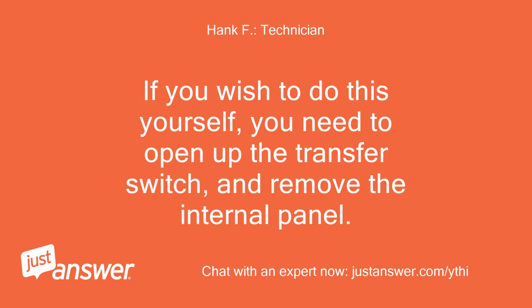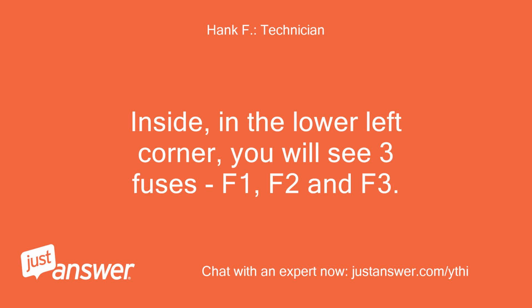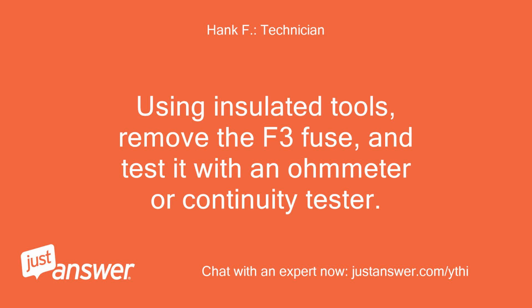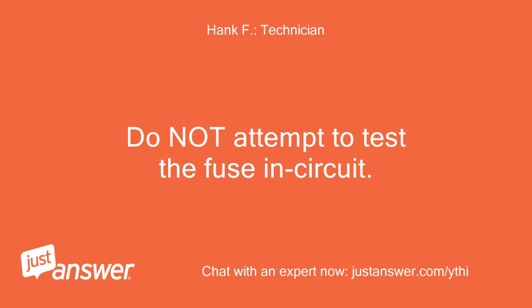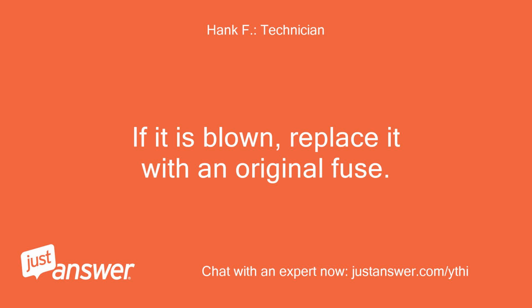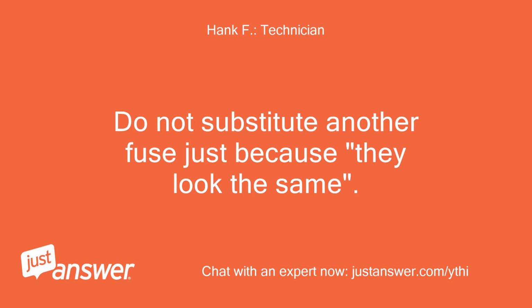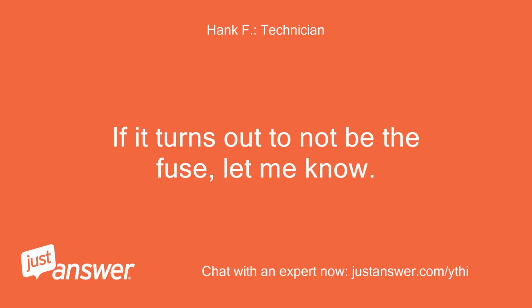If you wish to do this yourself, you need to open up the transfer switch and remove the internal panel. Inside, in the lower left corner, you will see 3 fuses, F1, F2 and F3. Using insulated tools, remove the F3 fuse, and test it with an ohm meter or continuity tester. Do not attempt to test the fuse in circuit. If it is blown, replace it with an original fuse. Do not substitute another fuse just because they look the same. If it turns out to not be the fuse, let me know.